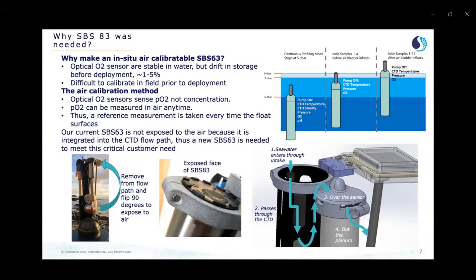So our current 63 is unfortunately not exposed to the air. It's actually integrated in the CTD flow path. So we needed to design a new sensor, which is the SBS 83. Essentially what we did was we took the 63 out of the flow loop, we flipped it 90 degrees and put it on the mast of the float, which now exposes the face of the sensor to air every time it emerges from the water.